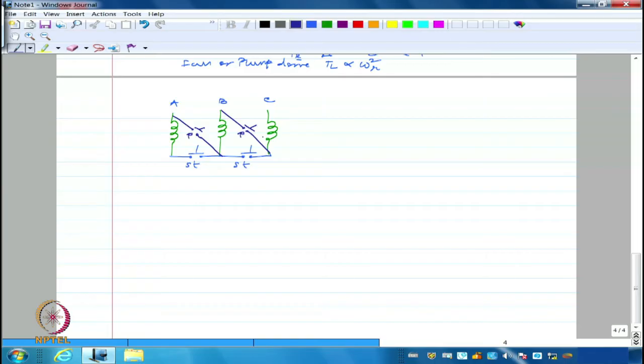So this will again be a running contactor. And the third one has to be connected basically between this and this. Right? This will be another running contactor. So the starting contactors will be opened, the running contactors will be closed, and then it will become connected automatically in delta, and then it will pick up a higher torque after that. Right? So star delta starting is very, very commonly used in agricultural pump sets.